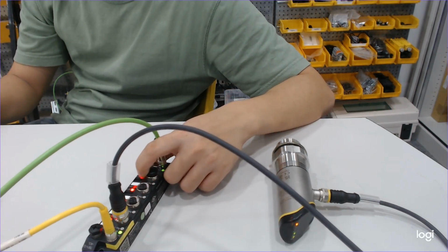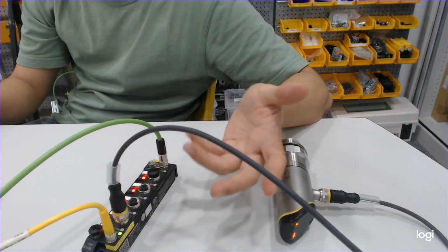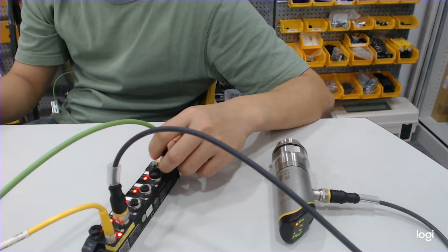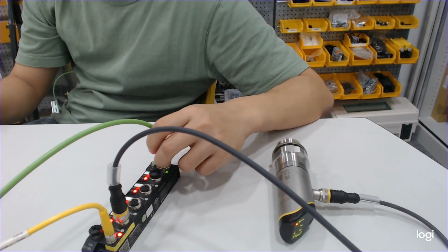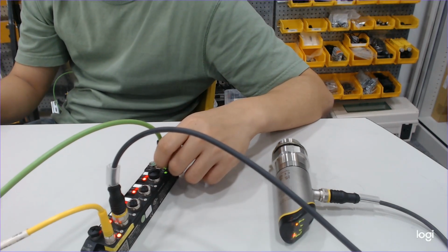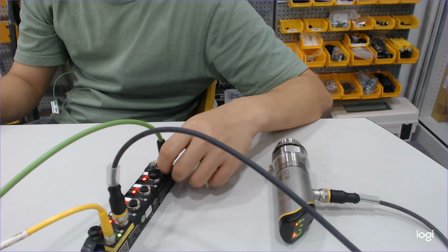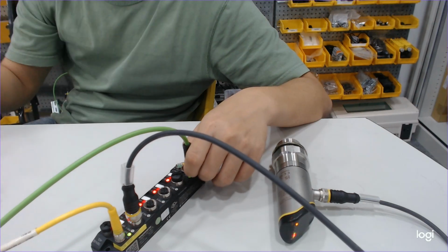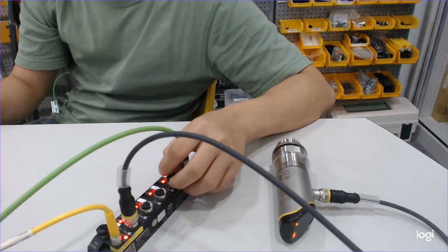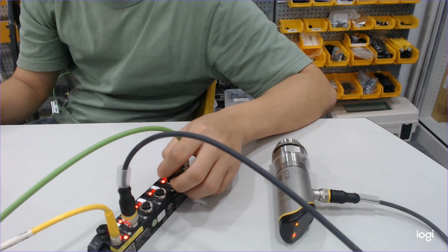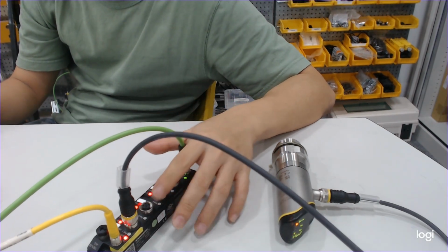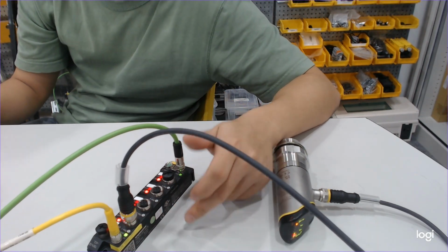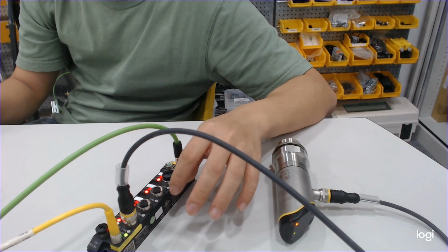But let's say I don't have access to this web server. What else am I going to do if I want to continue to get information? For me, there is a method that I prefer to use. It's through Modbus TCP. So I'll be able to use a Modbus poll app to actually directly connect an Ethernet cable to my computer, and I can see what is going on within the module. Right, so the errors will be saved inside certain registers, and we can always look at that particular register to figure out what is going on with the device.